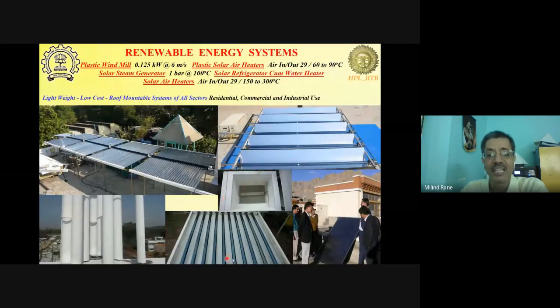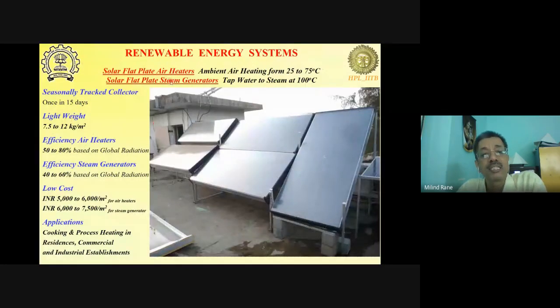Okay. And then, of course, we had a solar refrigerator cum water heater, as I told about, with an activated carbon ammonia-based refrigeration system deployed inside the evacuated glass tubes here. And that would produce ammonia. It will condense and give us cooling. And that cooling would be stored in the ice bank tank inside the refrigerated cabinet, which would maintain the refrigerated cabinet cool throughout the 24 hours. Okay. And the heat of adsorption would be recovered as hot water for bathing and other applications for a residential water heater cum refrigerator.